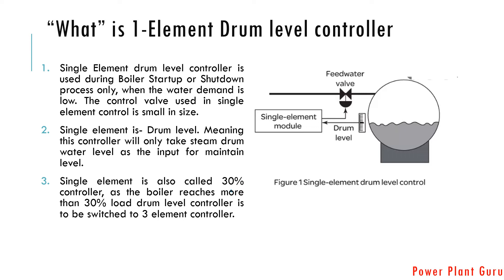The controller — meaning the control system — tells the control valve how much it should open or close to maintain the level. This controller only looks after the boiler steam drum level, and based on the level it gives a signal to the control valve supplying feed water to the boiler. For example, if you set a 50% drum level set point and the level goes to 55%, it will close the valve; if the level drops to 40%, it will open the valve. This level control is only looking at the drum level.